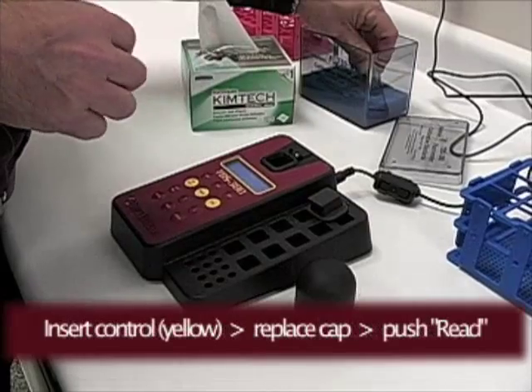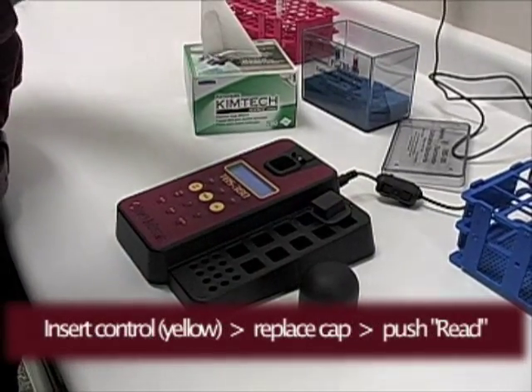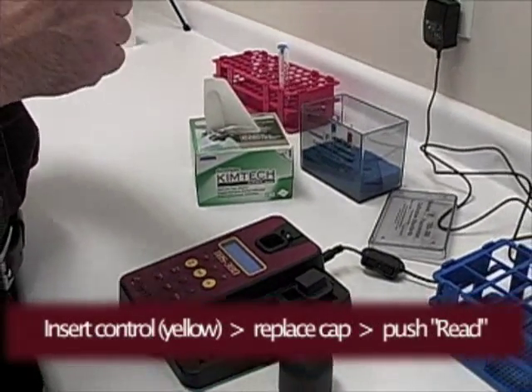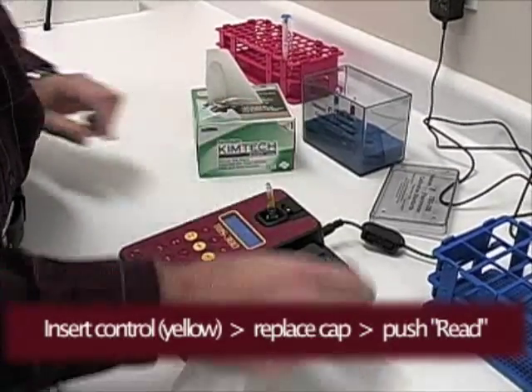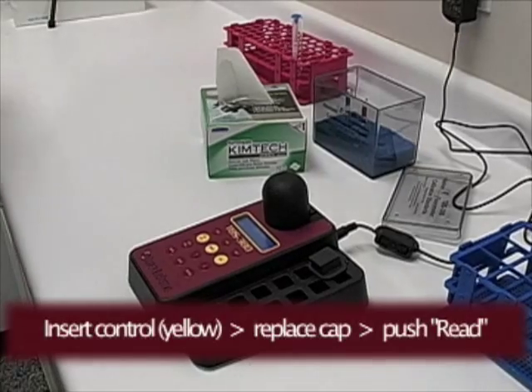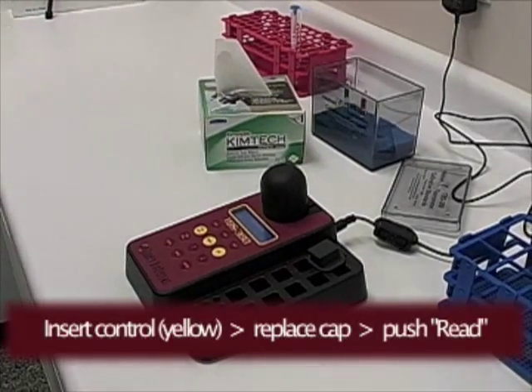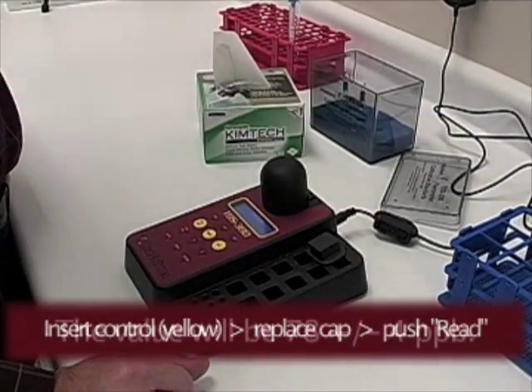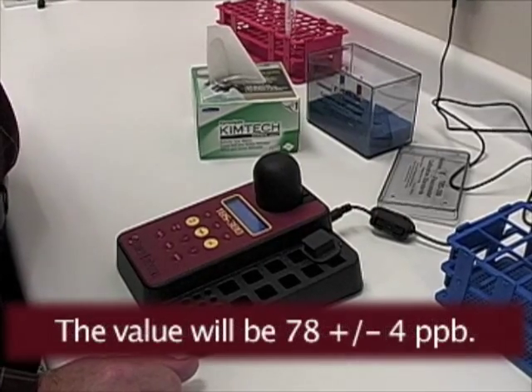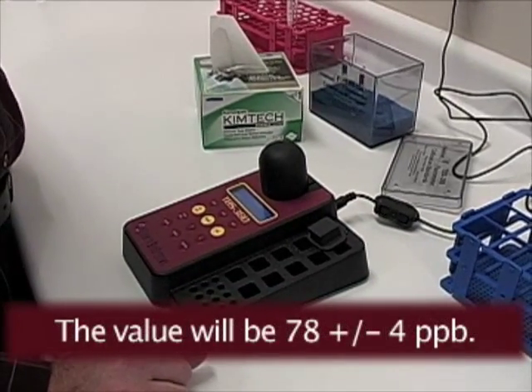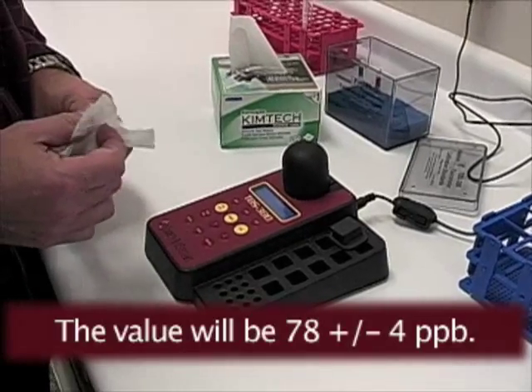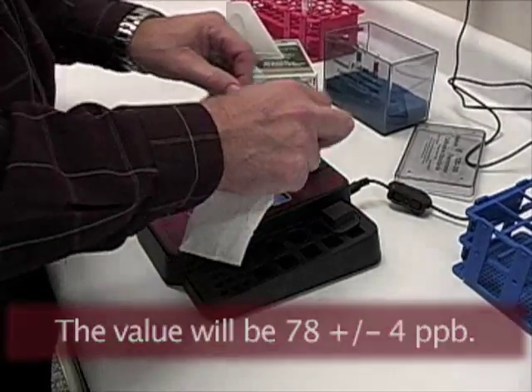Remove the calibrator, put the control in, put the cap on top, and hit read. The value will be 78 plus or minus 4 parts per billion. That way you know you have the proper calibration.